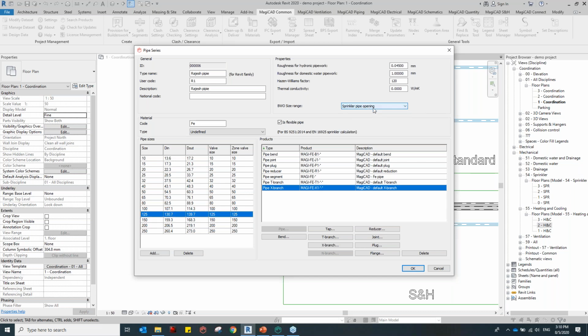You can also set up your pipe sizing openings - later we're going to see where we can set this pipe size opening data. Other than that, since we're talking about calculation, when you want to do the engineering calculation, you must have technical information such as roughness values for domestic water and the Hazen-Williams formula if you're using that to calculate, and thermal conductivity values if you use the Darcy-Weisbach formula. These are the basic technical information we need to feed into the pipe series. This information can be fed earlier or later, but before you do the calculation, this data must be present.